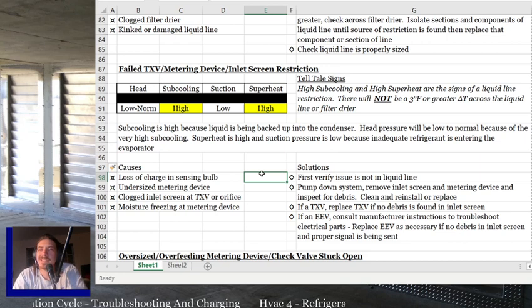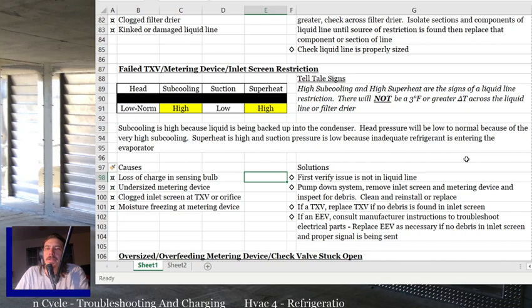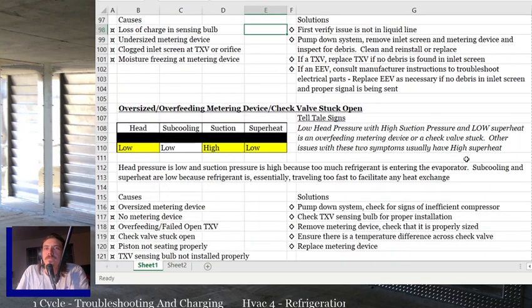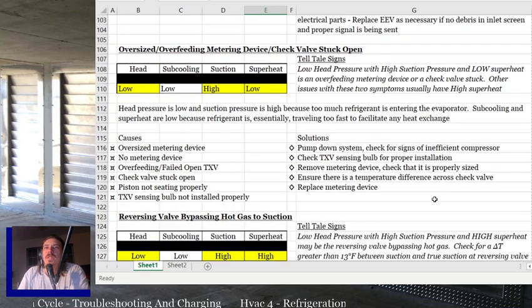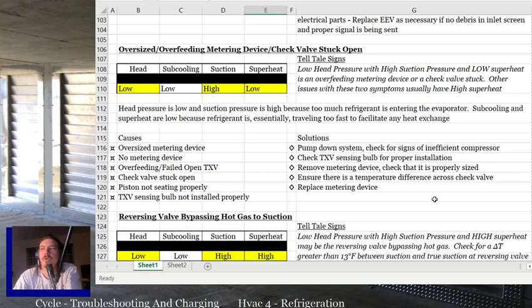If it's an EEV, an electronic expansion valve, consult the manufacturer's instructions to troubleshoot the electronic components of the EEV. Replace it as necessary if there's no debris in the inlet screen and a proper signal is being sent to the EEV. Next one is an oversized or overfeeding metering device, or a check valve stuck open.